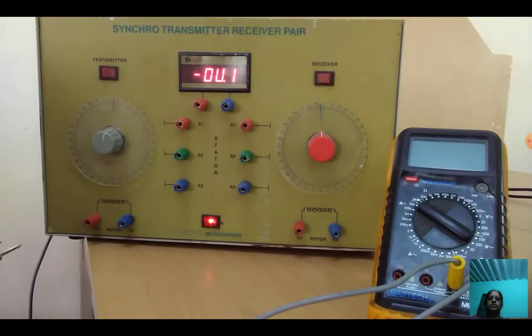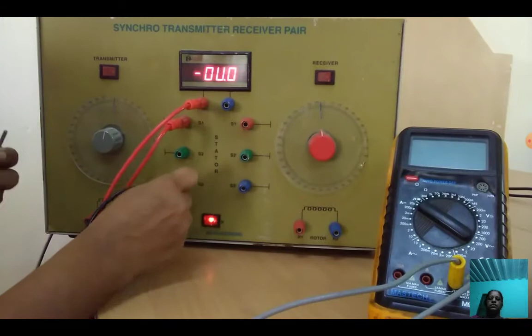Now remove the connections and check the stator voltage. S1 is connected to one terminal of the voltmeter, and S3 is connected to another terminal of the voltmeter. Switch on the supply, switch on the transmitter, and set it to 0 degree.